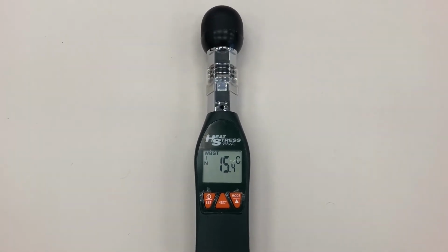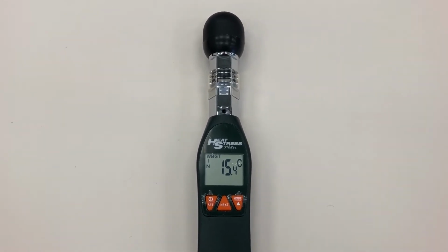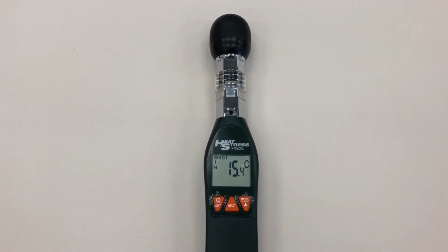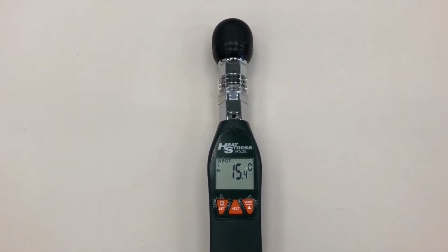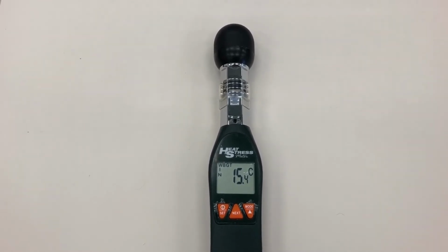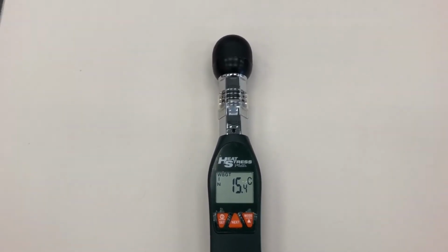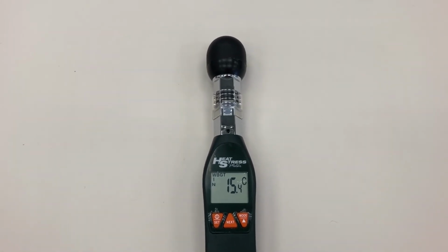Our third thermal tool is the heat stress wet bulb globe temp meter. And so it's going to measure temperature, humidity, and radiant heat. It's an index of environmental heat stress that accounts for ambient air, that being the dry bulb, relative humidity being the wet bulb, and the radiant heat measured in the black matte radiant heat globe, or the sphere there.